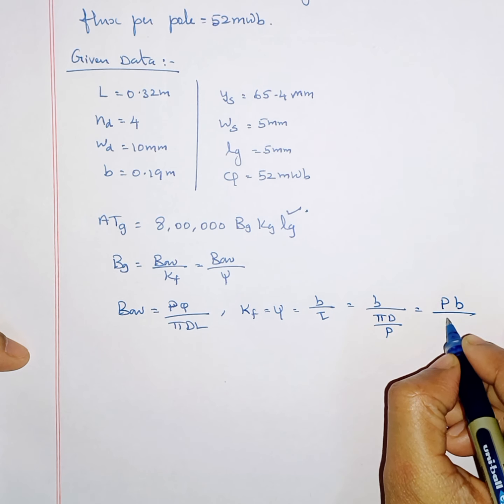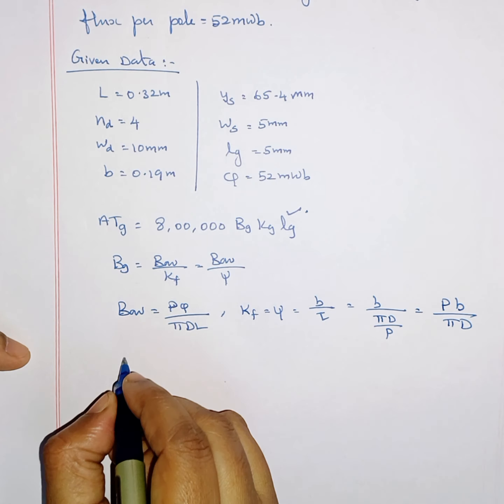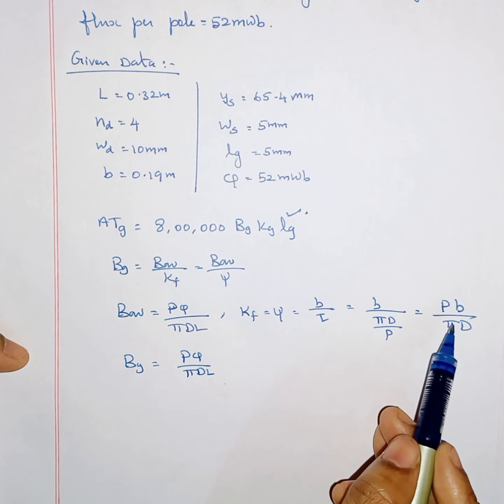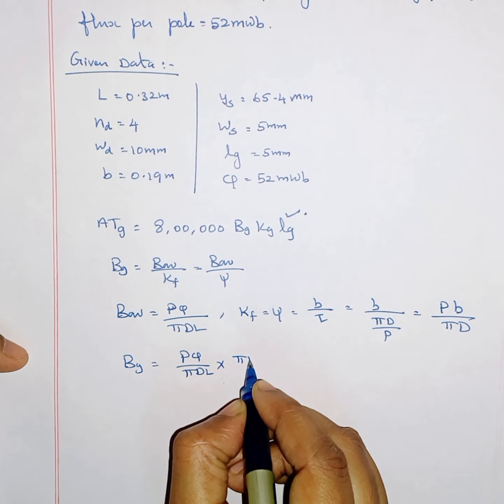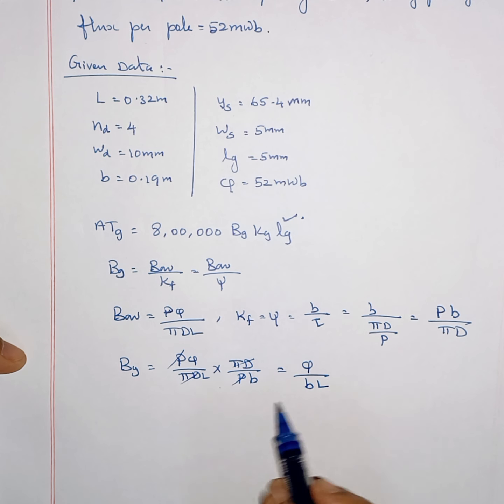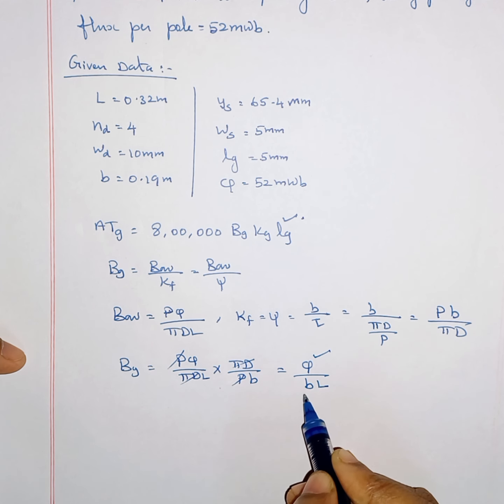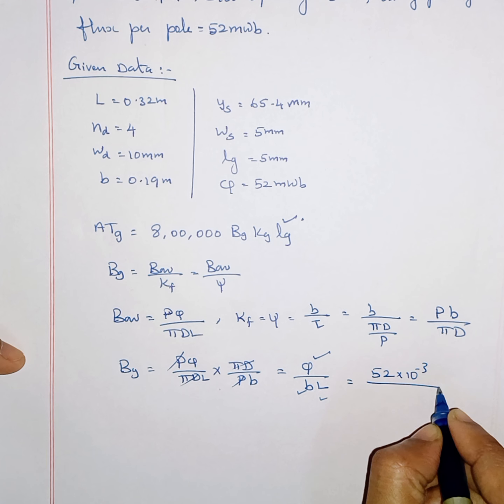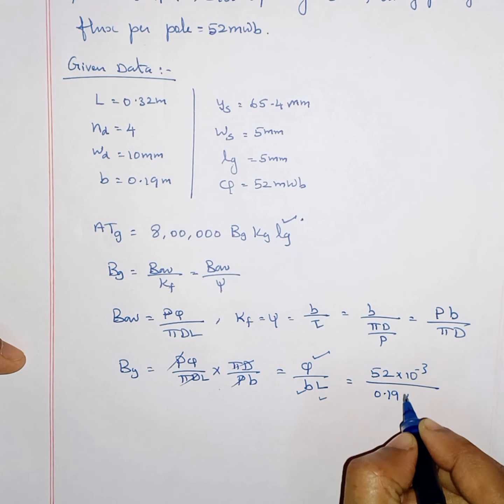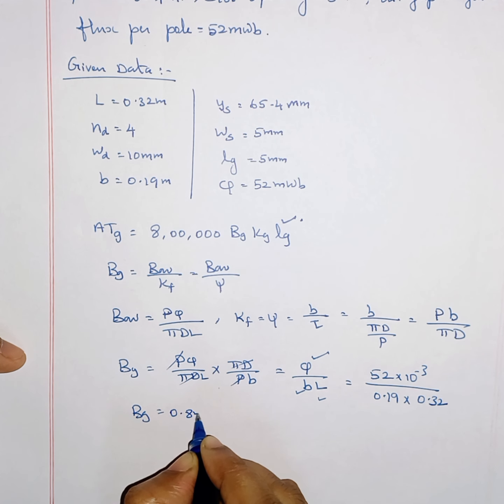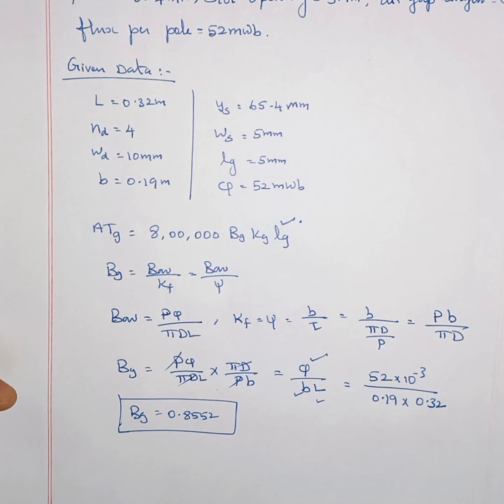Rewriting this, we get P·B divided by π·D·L, and the denominator psi is P·B divided by π·D, so we can rewrite this as π·D divided by P·B. The P·P gets cancelled and π·D·π·D gets cancelled, giving BG equals φ divided by B times L. Substituting: 52 into 10⁻³ divided by B value 0.19 and L value 0.32 — we get BG equal to 0.8552 Tesla.